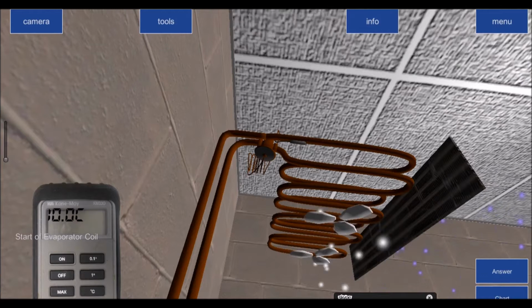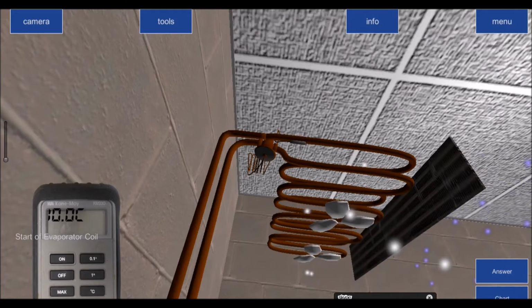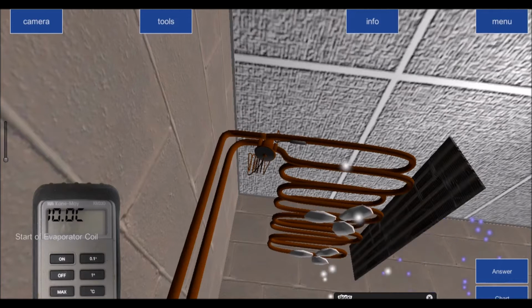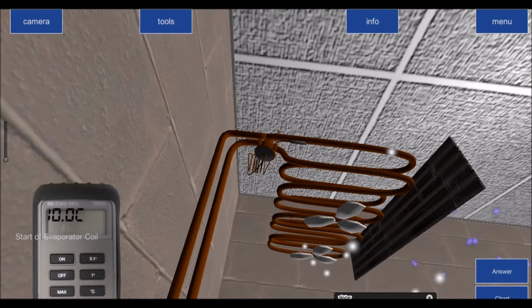And for a refrigeration system such as this one, which is just your standard chilled cold room, so for any commercial refrigeration system, your domestic fridge, your ice bank, even your water chillers, well, not water chillers because water can be 10% more efficient, but in some cases your water chillers, I'll come back to you on that one. Your beer coolers, your butcher's cold rooms, and so on and so forth, your refrigeration systems, even your ice cream freezers, the delta T total should be between 5 and 10 degrees of a difference.